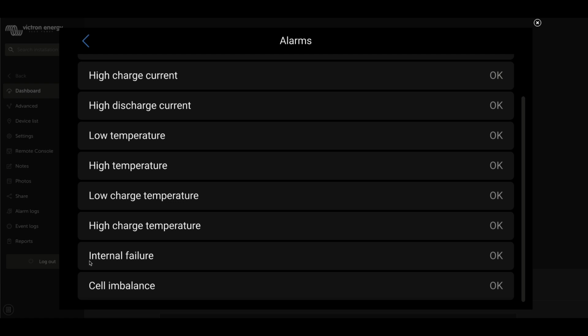Internal failure is not always going to be something catastrophic. Sometimes this indicates that there's a communications issue between batteries. Simplest example being a cable got disconnected for some reason. Either somebody was doing some maintenance on the system and didn't connect the batteries back together, or connected them in the wrong order, or a mouse chewed through a cable, or some other indication like that. It's also a bit of a catch-all. If there is something that the battery is noticing is wrong, but it doesn't have it fully set up to tell the system exactly what that is, it may tell you that there's an internal failure.